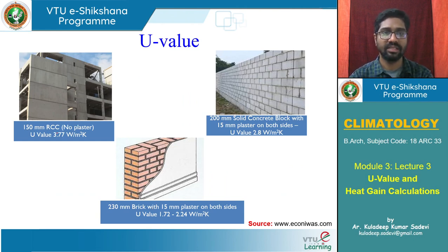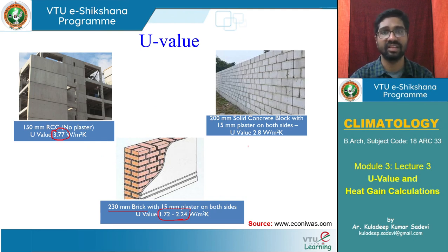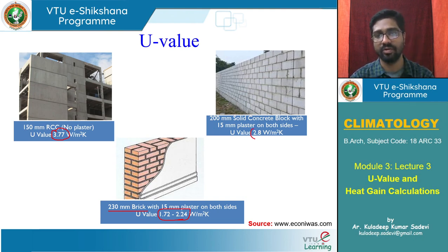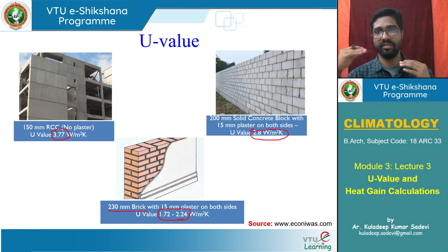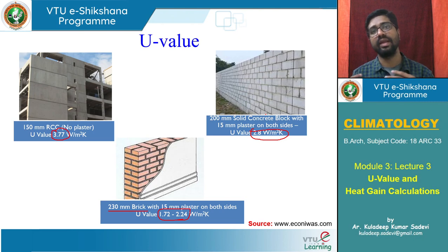For comparison: 150 mm RCC has 3.77 W/m²·K; a 9-inch brick wall is 1.72–2.24 W/m²·K depending on density and manufacturing process; solid concrete blocks are about 2.8 W/m²·K. So the range goes from about 3.7 for concrete, to 2.5–2.8 for normal brick or cement bricks, and AAC blocks are in the range of 0.8–0.9 W/m²·K.